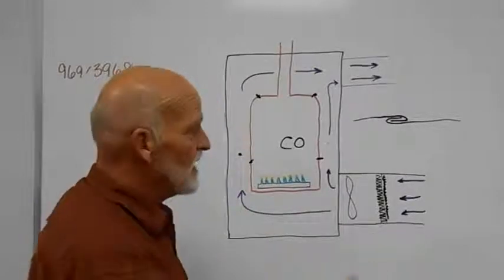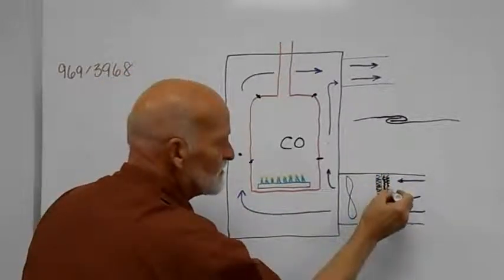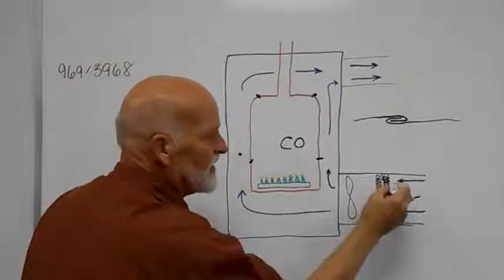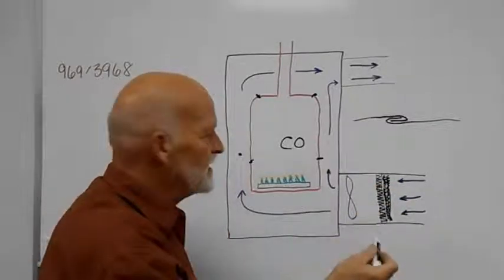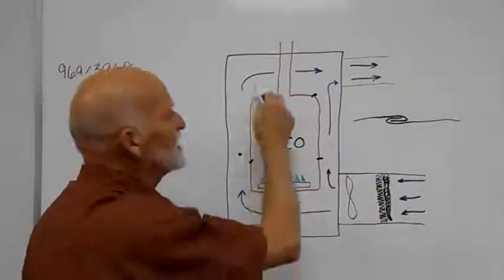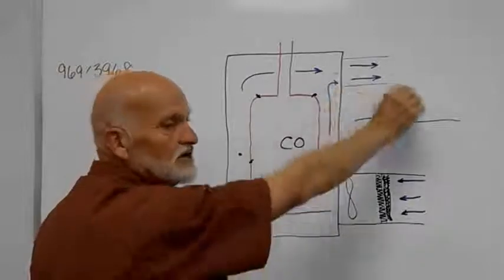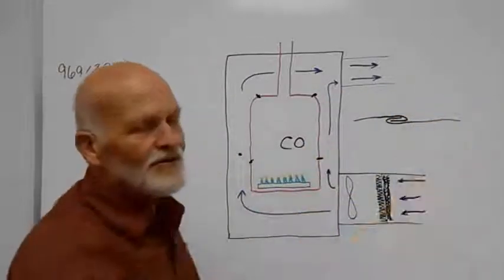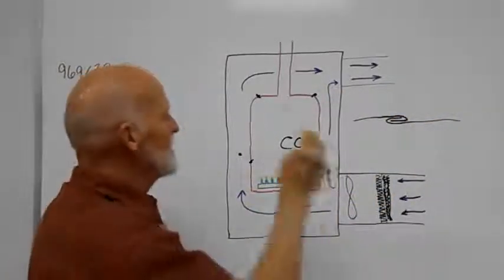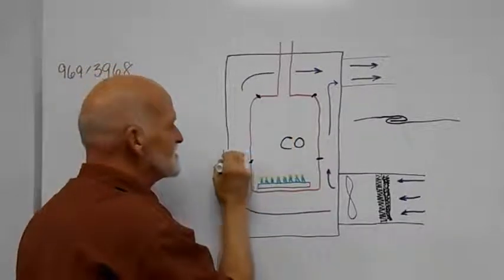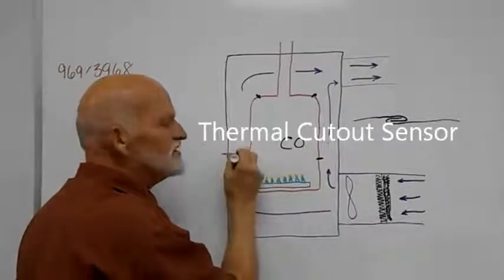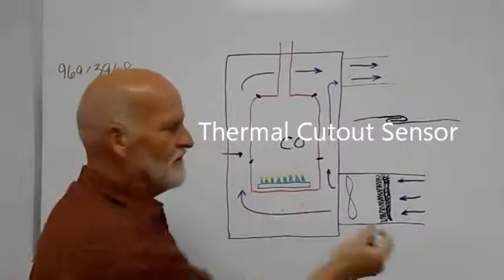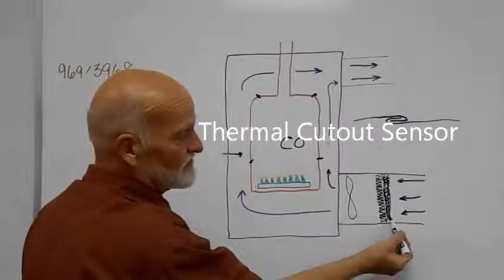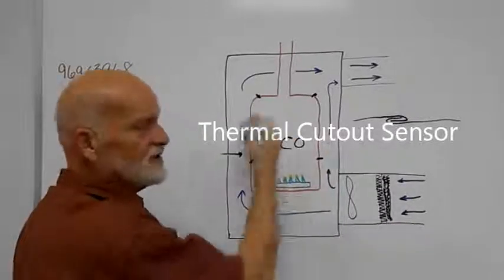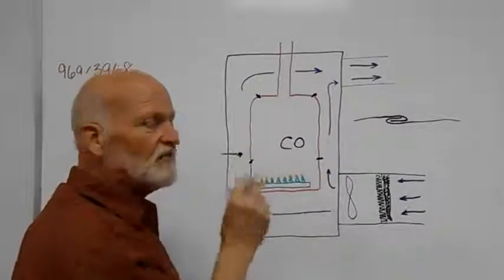Here's where the problem lies. When you load this filter up with a bunch of dirt on the front, air can't pass through as freely. The air cannot take the heat off of the exchanger and deliver it to you properly. Not only is that very inefficient, but they have a little sensor right here that senses this air, and if this air gets too hot, and it'll get too hot if this filter is clogged and air can't come across enough, it shuts down the furnace.